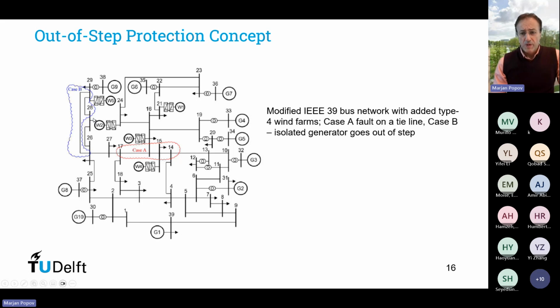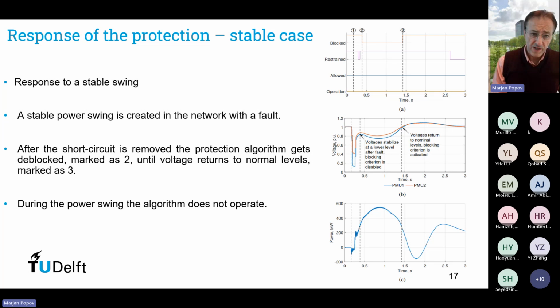So in the scope of this presentation, I will just refer to two cases, one stable and one unstable case, which have been done for case A, when the fault occurs on a tie line. So when a fault occurs on a tie line and is eliminated for several cycles so that we do not exceed the critical clearing angle, then we have a stable case. So this is actually what can be seen here.